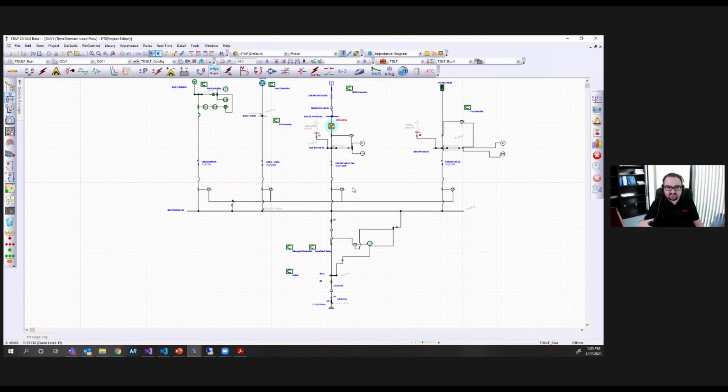And once it has this calculation, before the system goes to the islanded mode of operation, it can charge. As I mentioned, there's a logic behind the scenes that before the system goes to planned islanding or even unplanned islanding, it charges the batteries to maintain a certain state of charge level in the system at all times, so that once the system goes to islanded mode of operation, the battery can take care of the system during those hours.